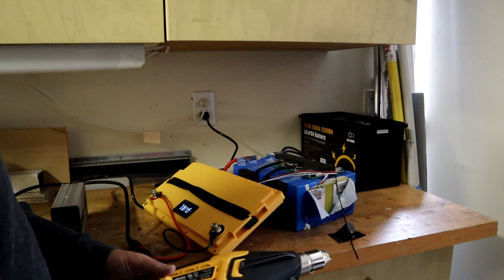The temperature specs for this battery are 0 degrees C to 45 degrees C, so you don't want to charge below 0 degrees C, and you don't want to charge or discharge above 45 degrees C. What I found was the low temperature cutoff seems set a little too low, somewhere around -7 degrees C, about 19 degrees Fahrenheit. Either that, or it takes a lot longer than a couple of minutes for the BMS to react and shut down. On the high temperature side it was a little difficult with the heat gun to control the temperature, and it's possible it actually cut out at about 45 degrees C. Again, there seems to be a little bit of a time delay.